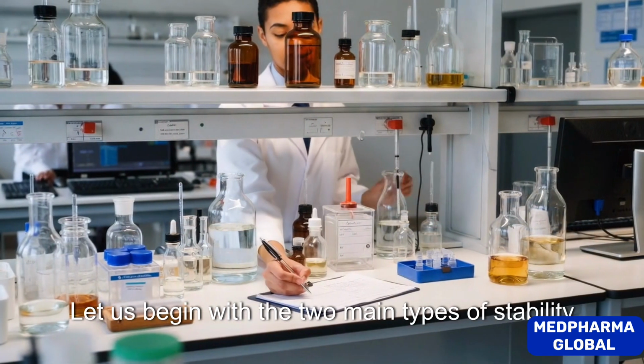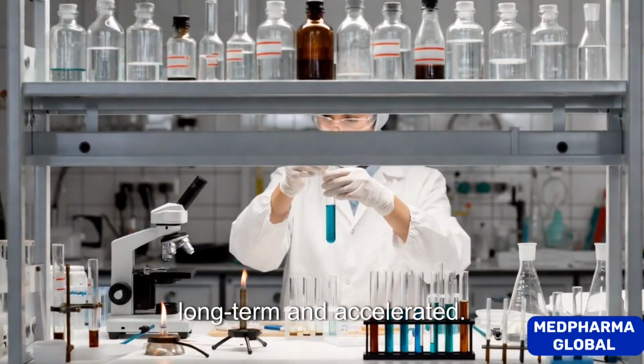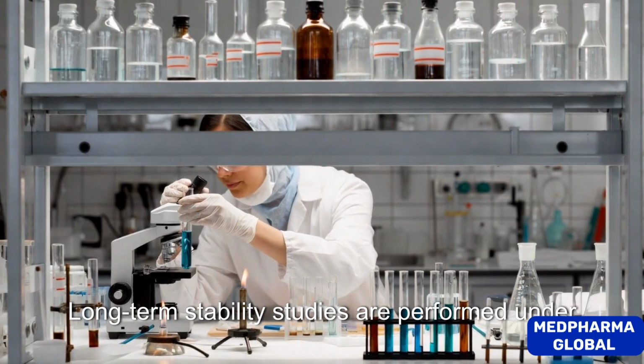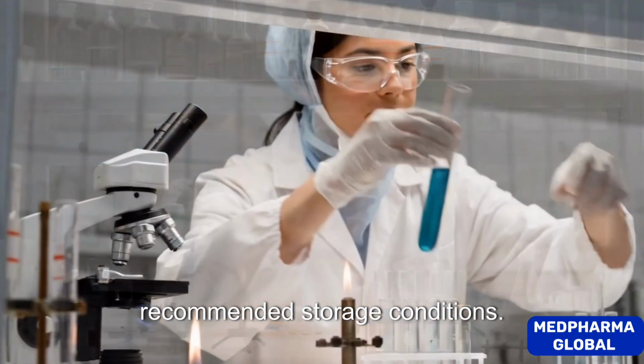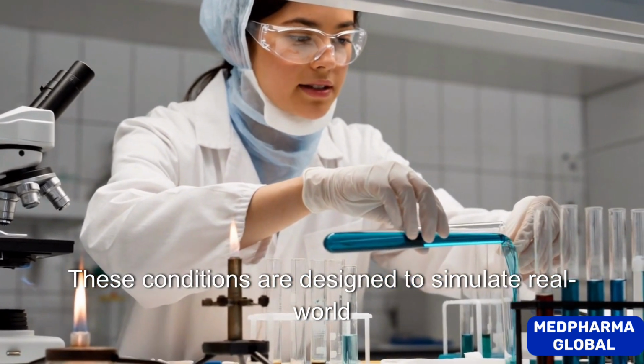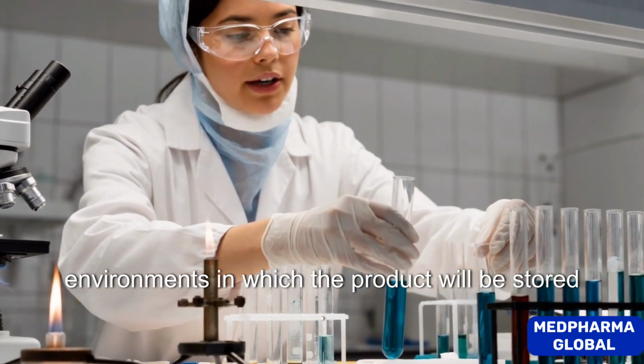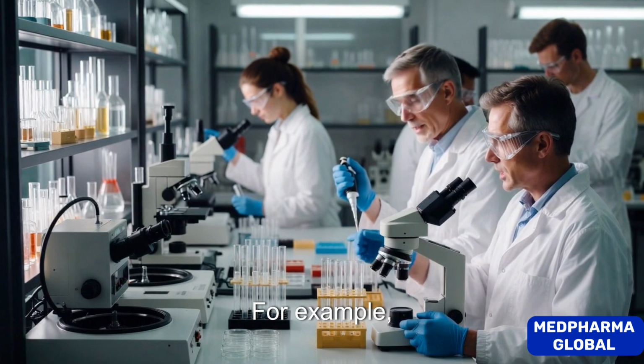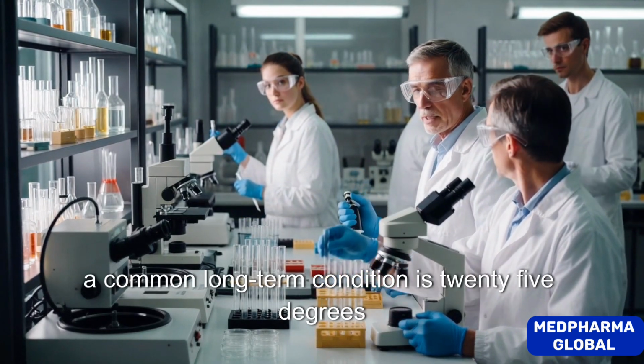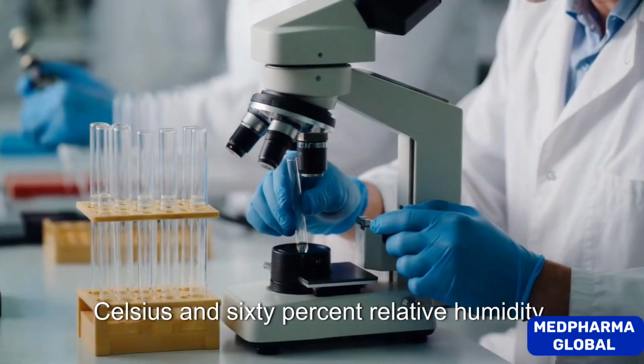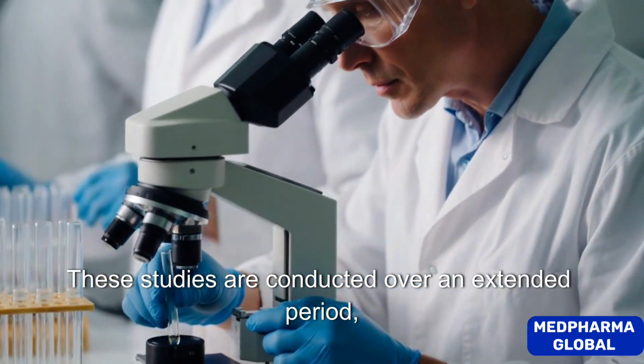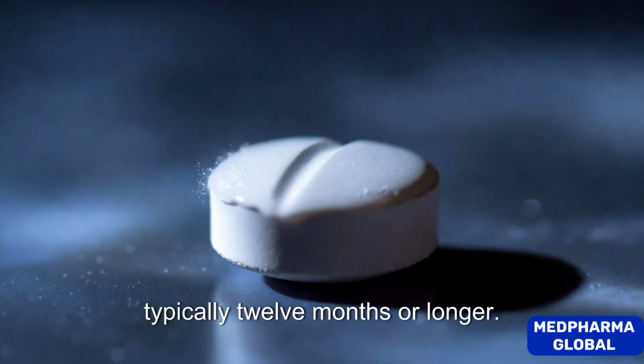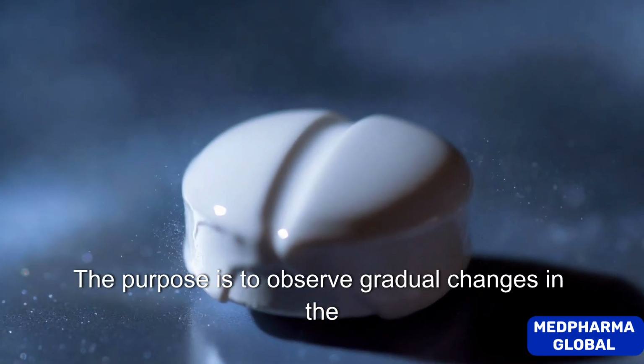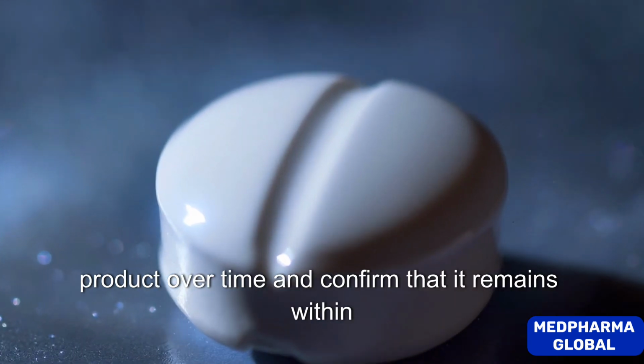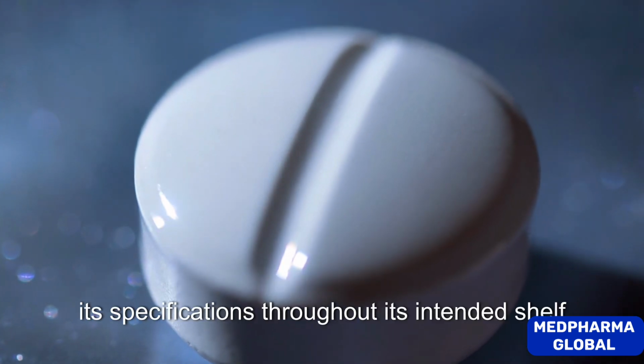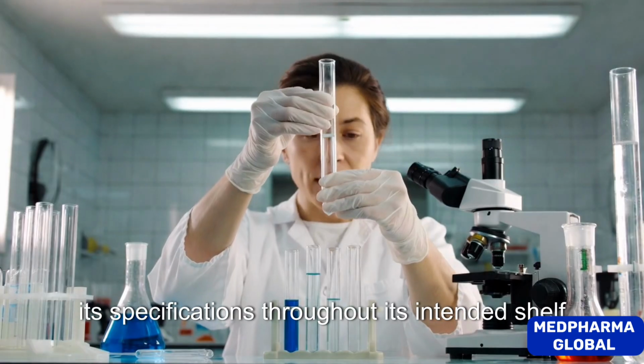Let us begin with the two main types of stability studies: long term and accelerated. Long term stability studies are performed under recommended storage conditions. These conditions are designed to simulate real world environments in which the product will be stored. For example, a common long term condition is 25 degrees Celsius and 60% relative humidity. These studies are conducted over an extended period, typically 12 months or longer. The purpose is to observe gradual changes in the product over time and confirm that it remains within its specifications throughout its intended shelf life.